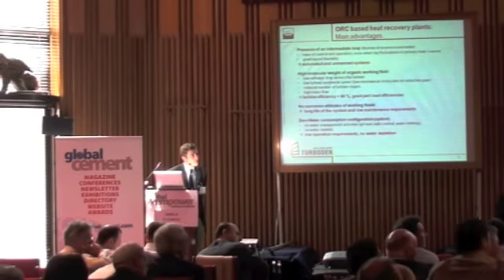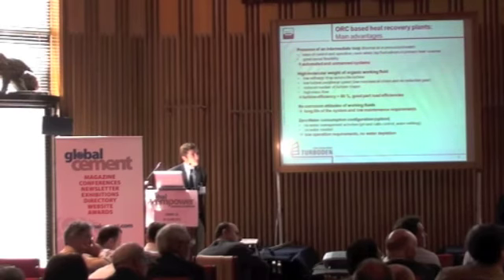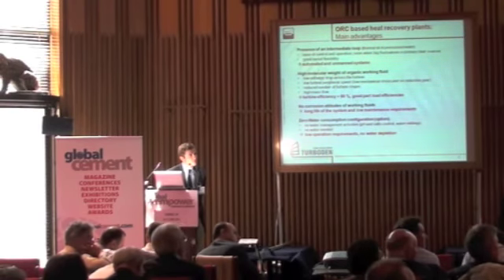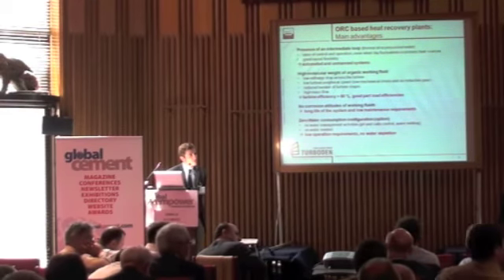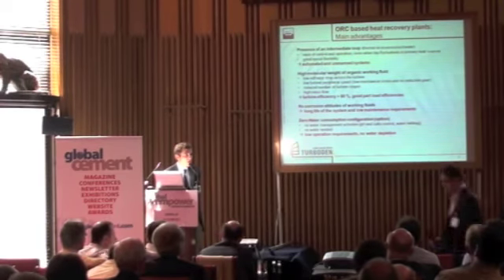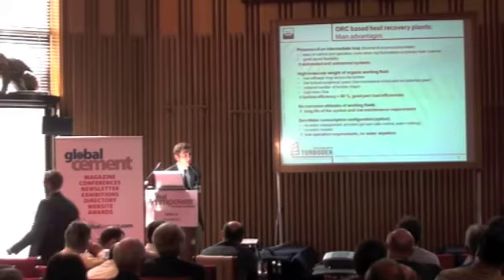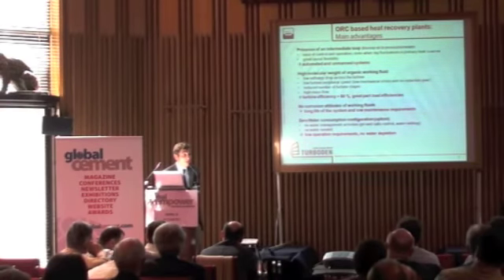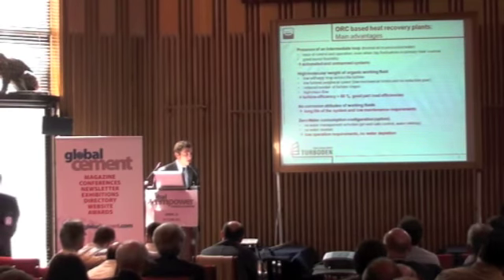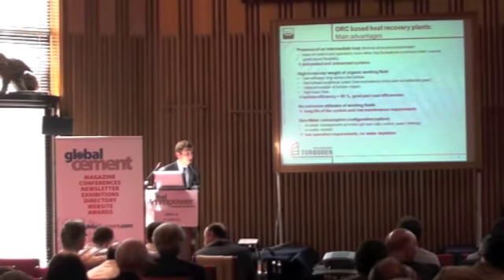And it looks like you are your own turbine manufacturer. My question is, how do you take care of leakage from the seal on your turbine? We have a double mechanical seal with the oil barrier, and we never experienced leakage of working fluid from the turbine seal or from the plant itself. We don't consider it as really an issue, so we really never faced that.